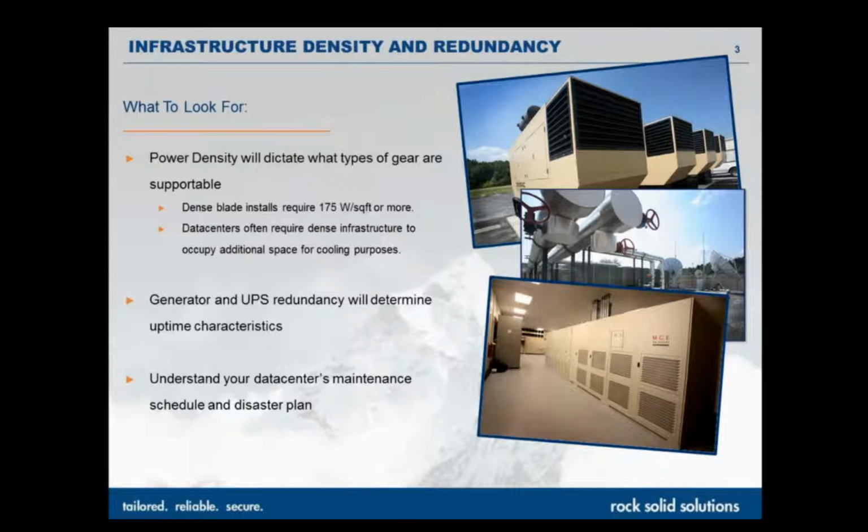The generators and UPSs are also key portions of the infrastructure. They're going to really determine exactly what your uptime characteristics are going to be. Generators being in a redundant fashion, having an N+1 configuration, and the same on the UPSs is going to be key as well. Making sure that during maintenance windows and during your maintenance schedules the redundancy is still there in case of a disaster. It's really going to increase your uptime capabilities and characteristics.